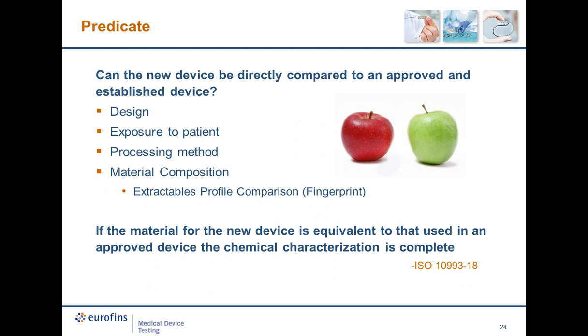An example of this could occur when the only difference between a new device and an established predicate device is that the new device will be introduced to the patient in a manner that lessens the patient risk. Since the predicate device has been established as more invasive and a higher risk to the patient, the chemical equivalence of the new device is met. If a sponsor can demonstrate that the material and risk for the new device is equivalent or less than the approved device, the chemical characterization is complete. That's why an emphasis should be put on using established materials and seeking out predicate devices.